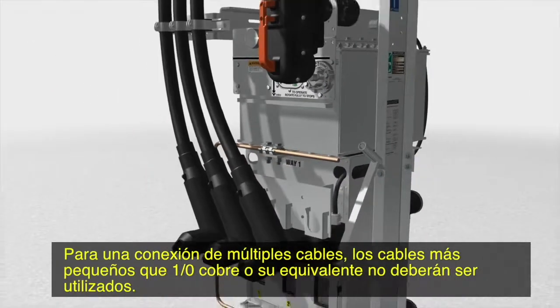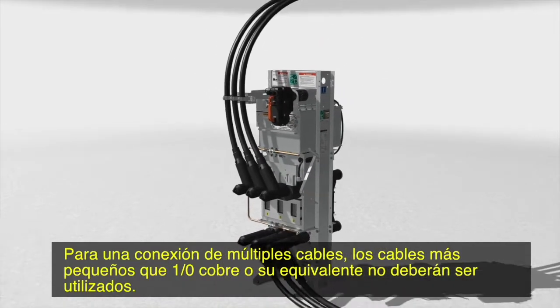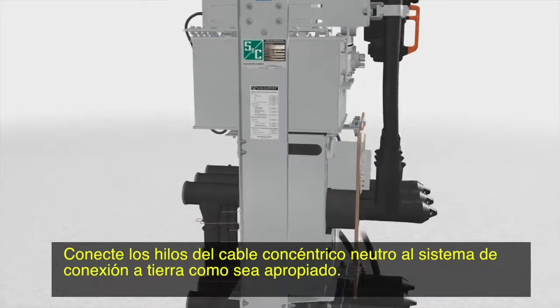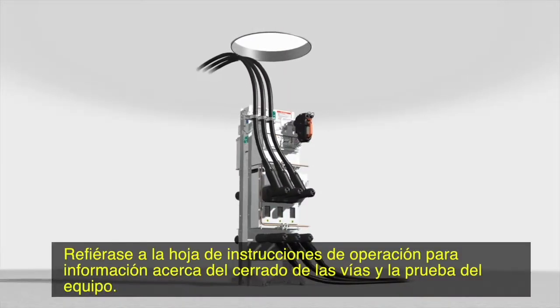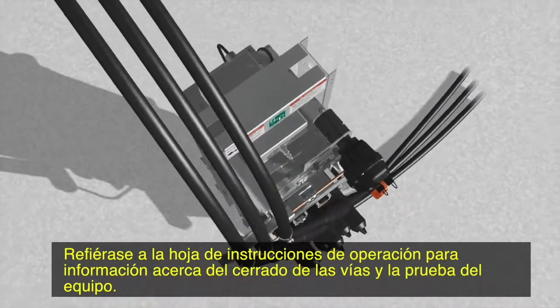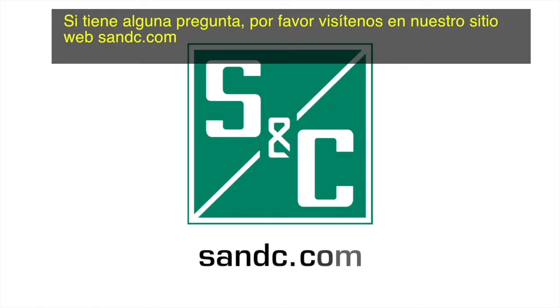For a multiple cable connection, cables smaller than 1-0 copper or equivalent should not be used. Connect the cable concentric neutral wires to the grounding system as appropriate. Refer to the operating instruction sheet for information on closing the ways and testing the switchgear. We hope you have found this video informative. If you have any questions, please visit our website at sandc.com.